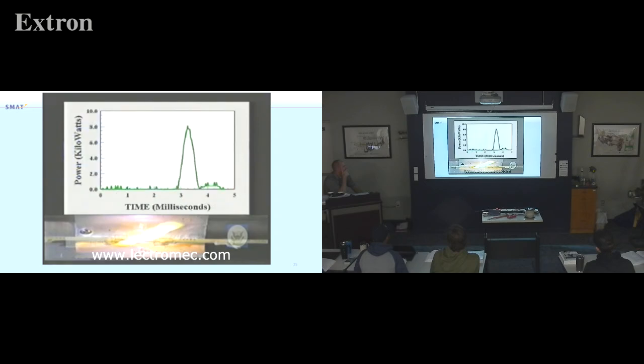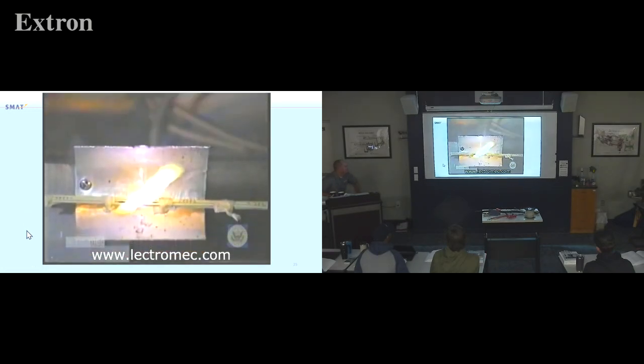From the voltage and current waveform, it is easy to determine the electrical energy in the flash. We see here the power spike during the flash is 8 kilowatts. The total energy in this flash was 4 joules, which is the energy needed to melt 6 milligrams of aluminum, equivalent to a fraction of a paperclip. Damage to the surrounding wires took time, but was documented during these tests.